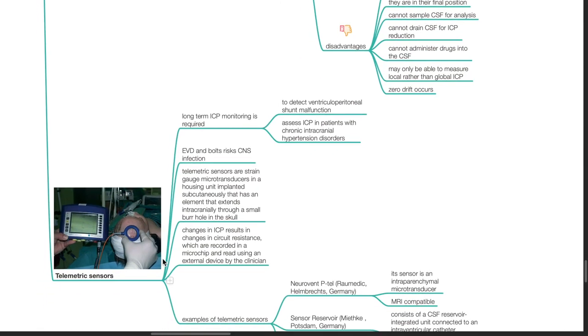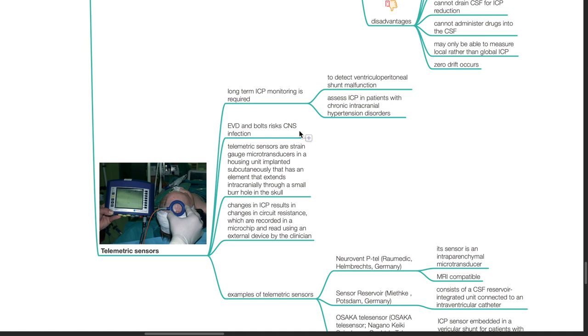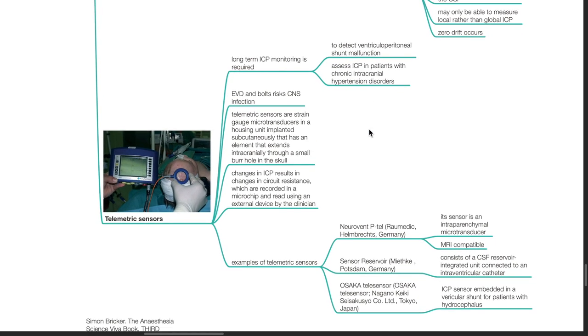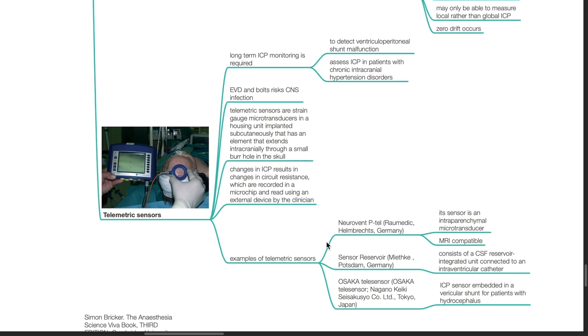Telemetric sensors. Long-term ICP monitoring is required to detect VP shunt malfunction and assess ICP in patients with chronic intracranial hypertension disorders. EVD and bolts risk CNS infection. Telemetric sensors are strain gauge microtransducers in a housing unit implanted subcutaneously that has an element that extends intracranially through a small burr hole in the skull. Changes in ICP result in changes in circuit resistance which are recorded in a microchip and read using an external device by the clinician. Examples of telemetric sensors include the Neurovent P-tel, Sensor Reservoir and Osaka Telesensor.